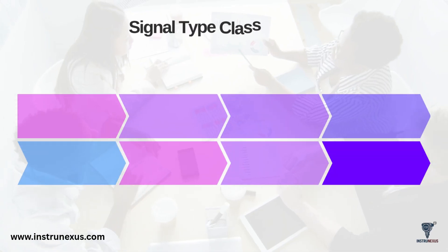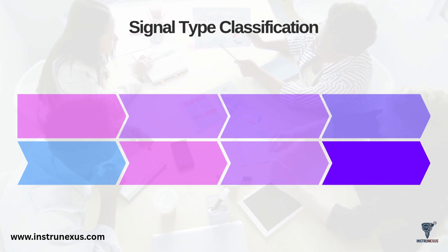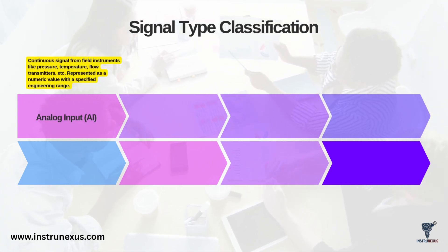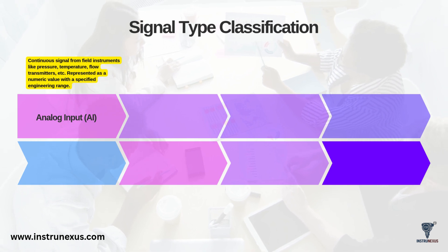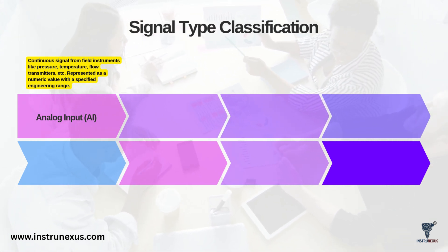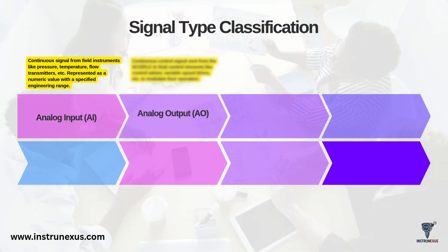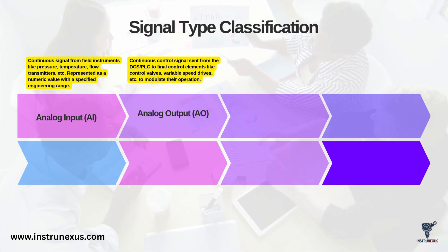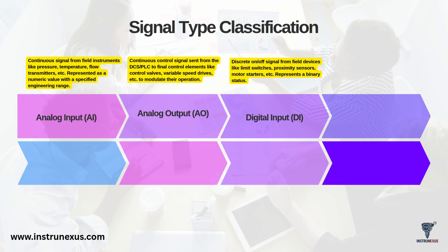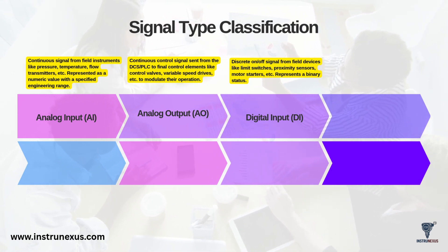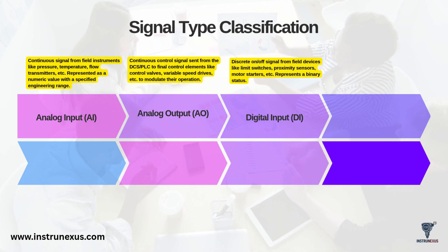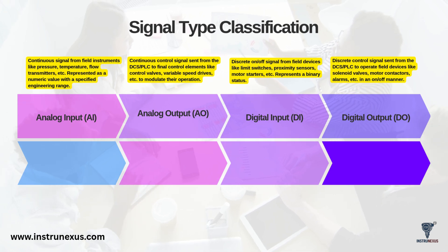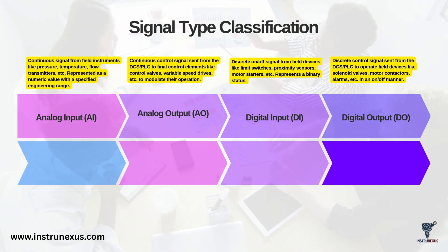Let's dig deeper into signal type, as it's the most fundamental classification. The four most common types are: analog input (AI) – a continuous signal from the field to the control system, like a pressure or temperature transmitter; analog output (AO) – a continuous signal from the control system to the field, used to modulate a device like a control valve; digital input (DI) – a simple on-off status signal from the field, like a limit switch or a motor run status; and digital output (DO) – a simple on-off command from the control system, used to operate a solenoid valve or start a motor contactor.